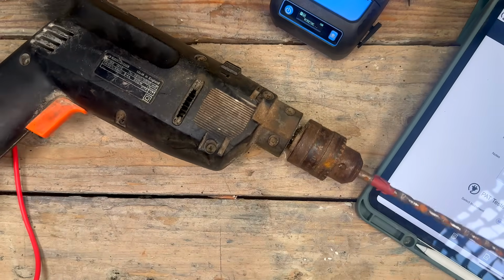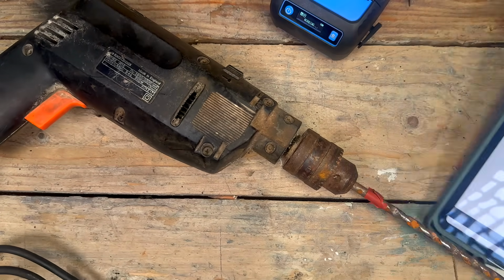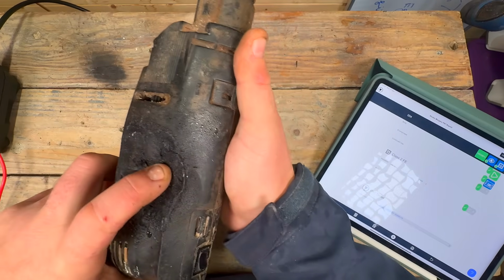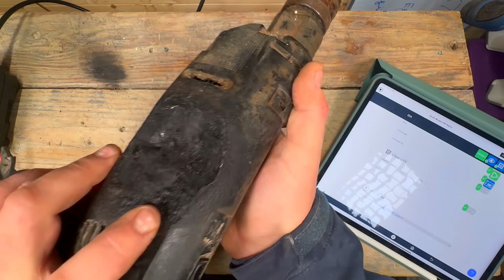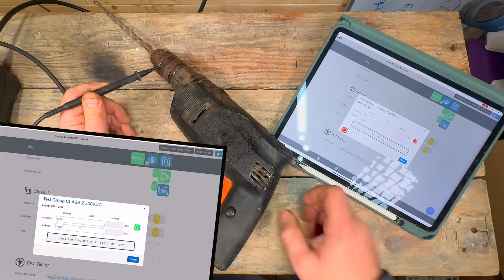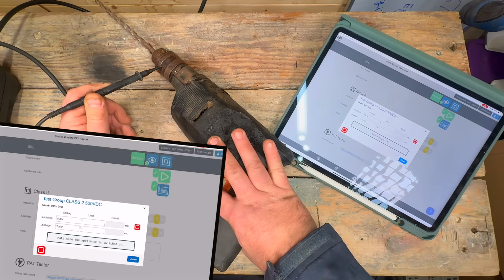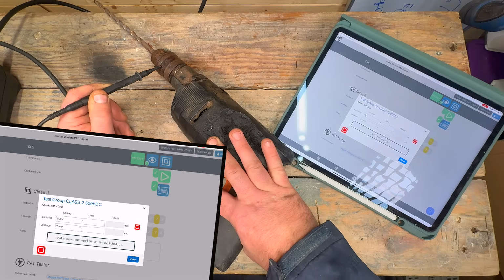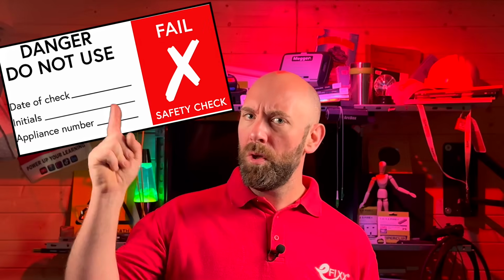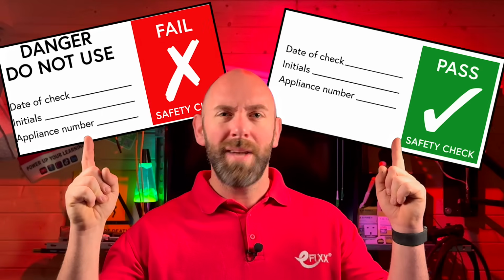Back in the studio, and we're going to test this class 2 drill. This is a good example of how insulation can break down over time, and we need to make an engineering judgment to either remove it from service or return. It passed the insulation resistance test, but it is obvious that heat damage is evident on the casing. But what would you do? Remove from service or remain in service? Let me know in the comments.